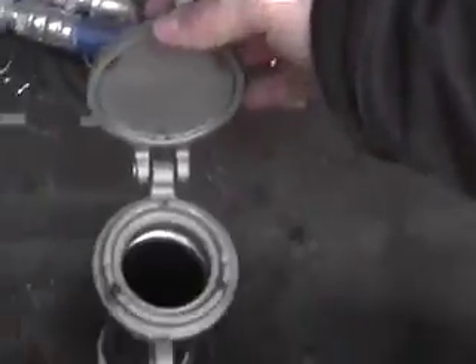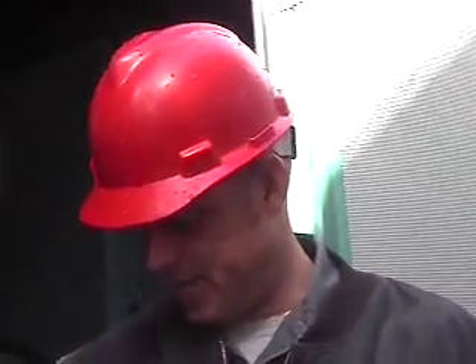Inside this door here is your fuel cap and fuel fill. Your fuel gauge is right here - you're sitting at just under three-quarters of a tank. This fuel tank has a capacity of 850 gallons. It's a dike tank, or it has a rupture basin in it, so if the inner tank holding the fuel ever leaks, it'll catch it in the outer tank.